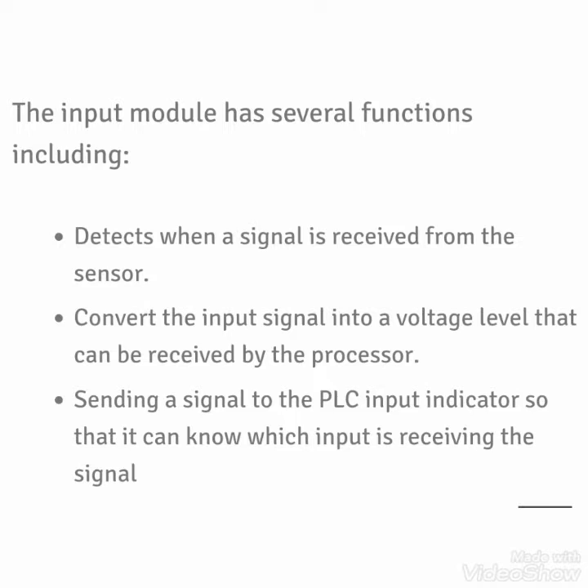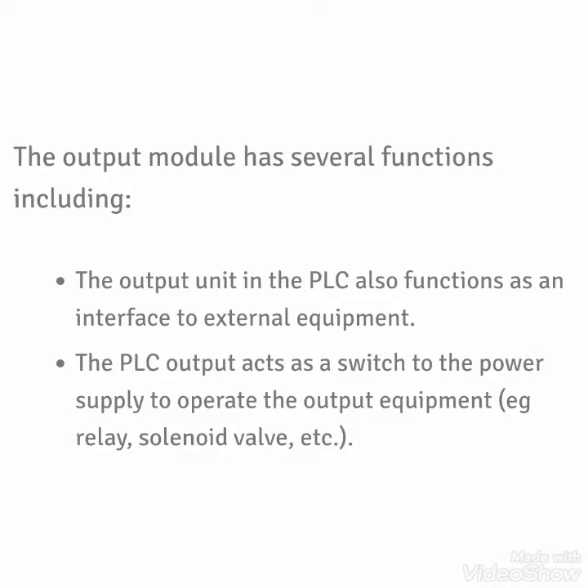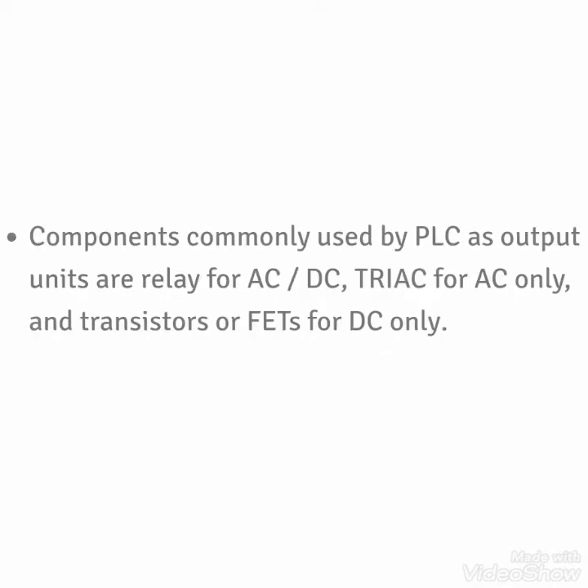The output module has several functions. The output unit in the PLC also functions as an interface to external equipment. The PLC output acts as a switch to the power supply to operate the output equipment — relay, solenoid valve. So the PLC will operate the relay, and after that relay we can take supply to the solenoid valve or anything we want.